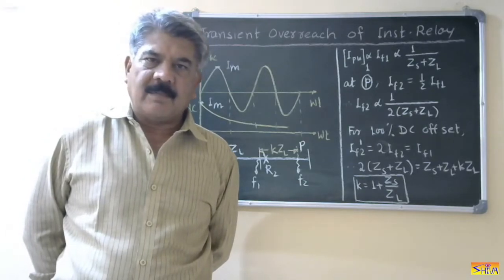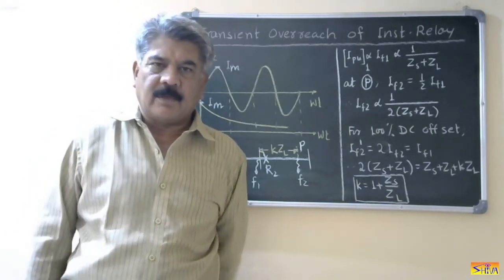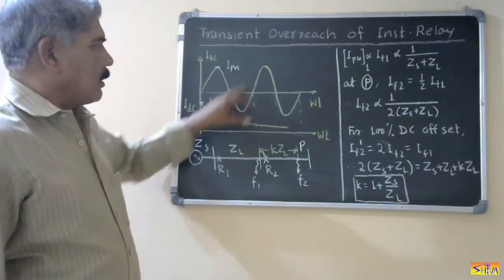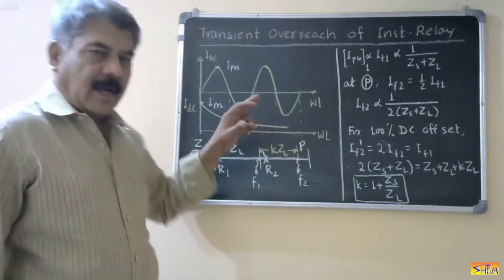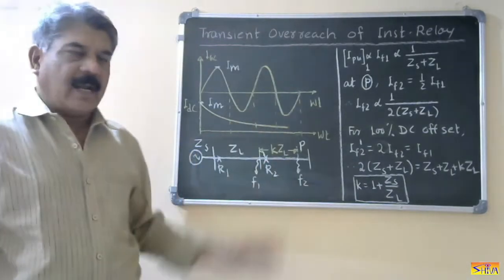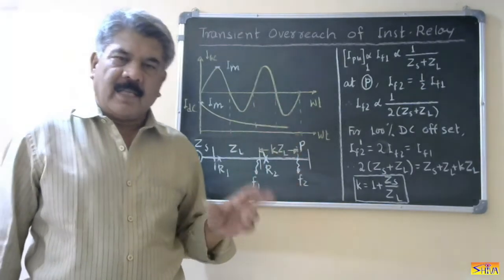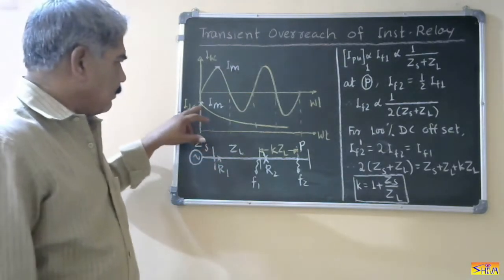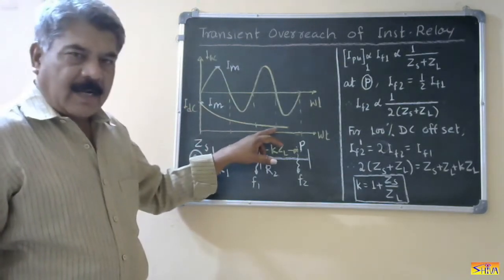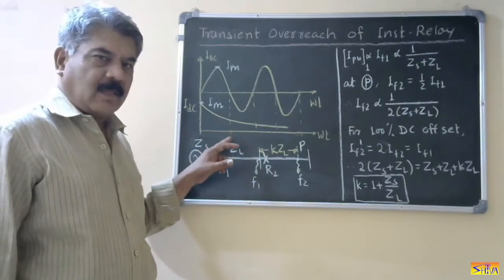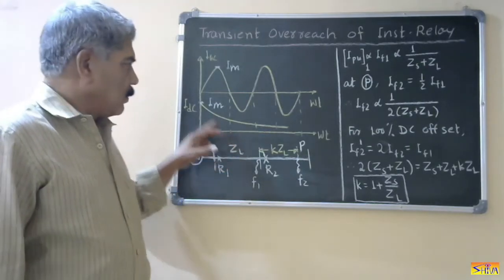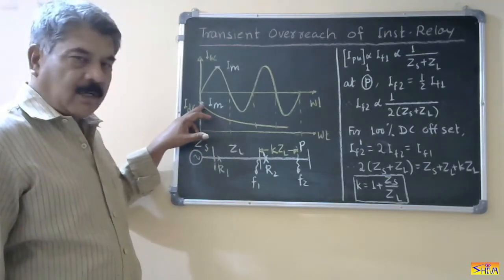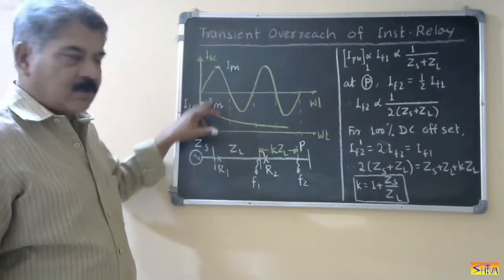First I will explain briefly what the DC offset of the fault current is. When a fault takes place, there is a sinusoidal component of the fault current. In addition to the sinusoidal component, there is one additional component of the fault current which is exponentially decaying, and it is called the DC offset of the fault current.